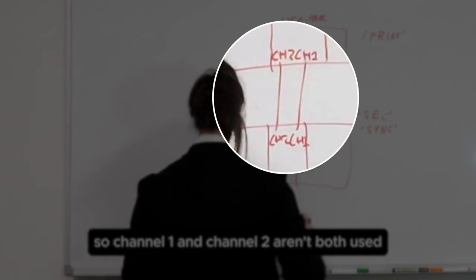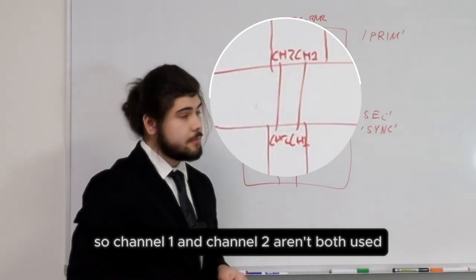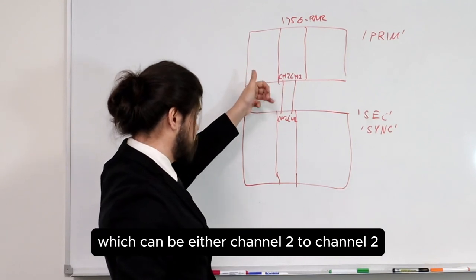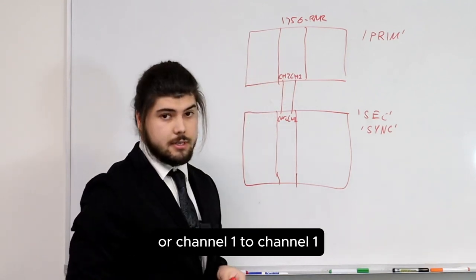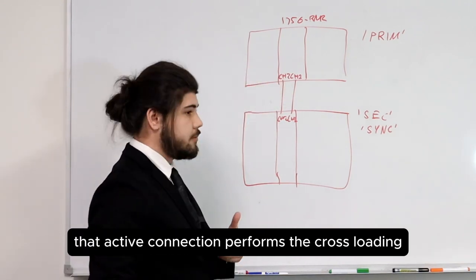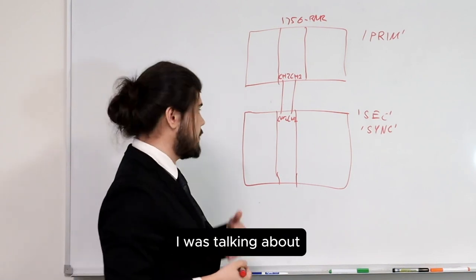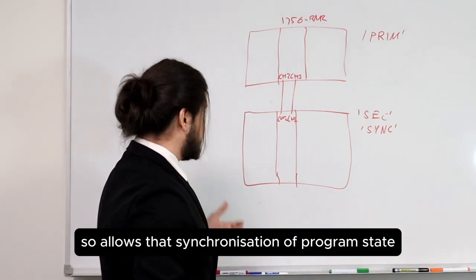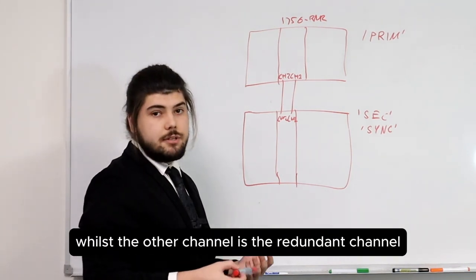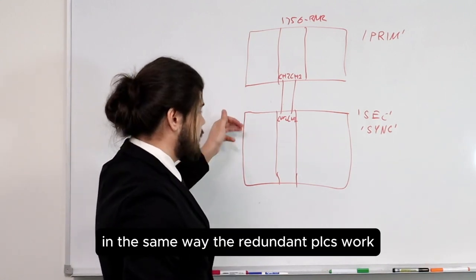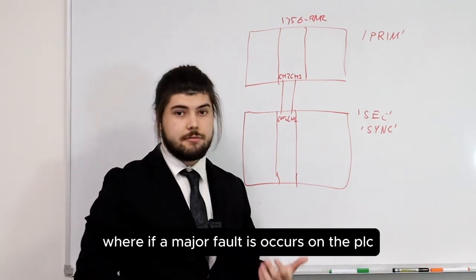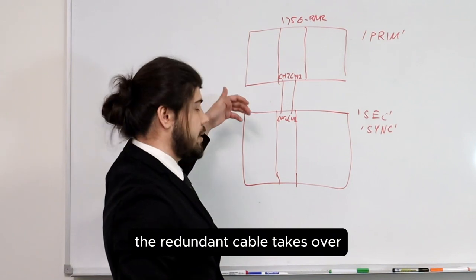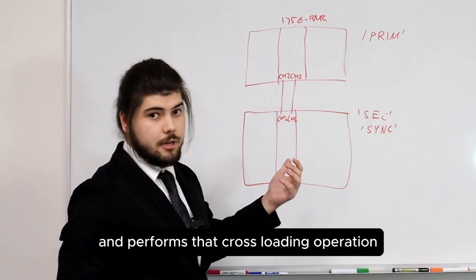Channel 1 and channel 2 aren't both used simultaneously. We have an active connection, which can be either channel 2 to channel 2 or channel 1 to channel 1. That active connection performs the cross-loading, allowing synchronization of program state, whilst the other channel is the redundant channel. In the same way the redundant PLCs work, if a major fault occurs on the PLC, the redundant cable takes over and performs that cross-loading operation.